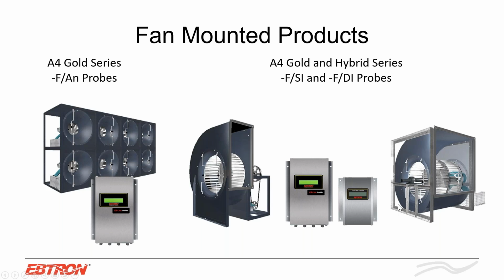We also measure in the fans, and we can do individual fan airflow measurement. And the great thing about this is these never need to be recalibrated. We can measure up to 8 individual fans for a fan array or fan wall configuration, get individual flow rates back to the transmitter, have analog and network output connections, whatever you need. And we also have a fan status alarm here. So you could set this fan wall and fan array up, and you could say, if any one of these fans gets outside a 20% predetermined set point, it alarms the transmitter, and you can take that alarm output to your system as well. So really great product. Again, these don't have to be recalibrated.